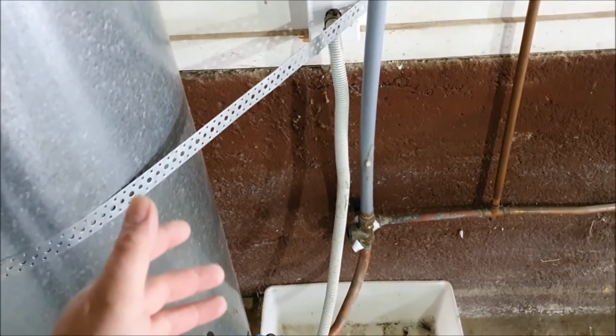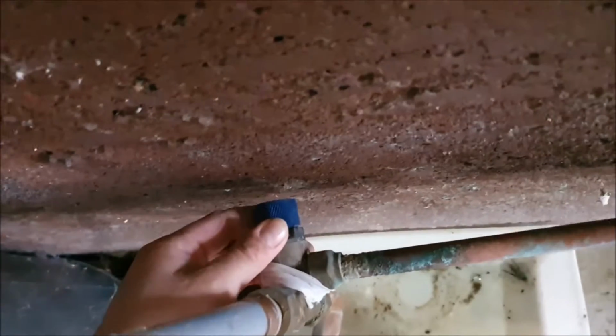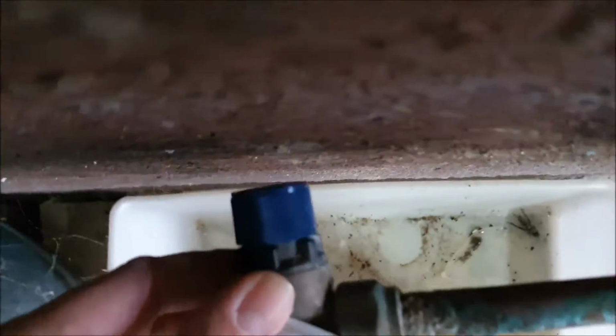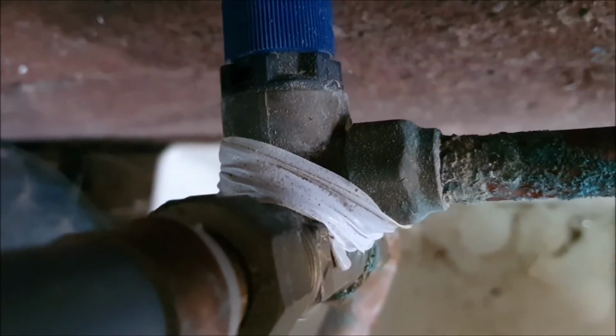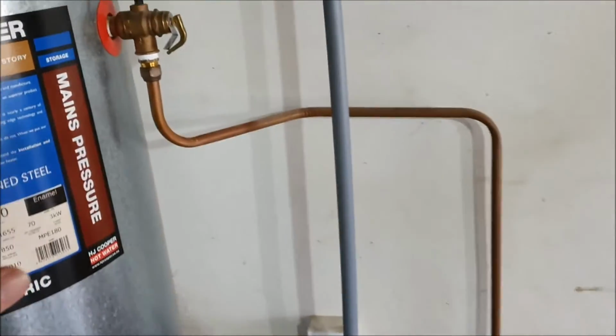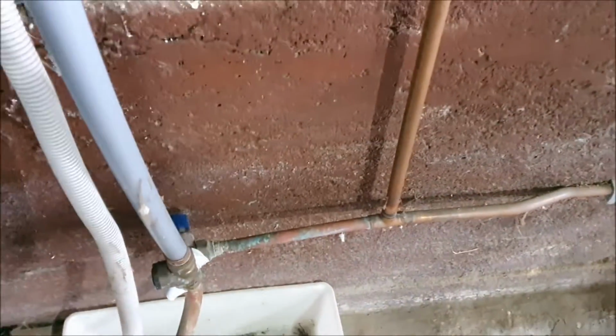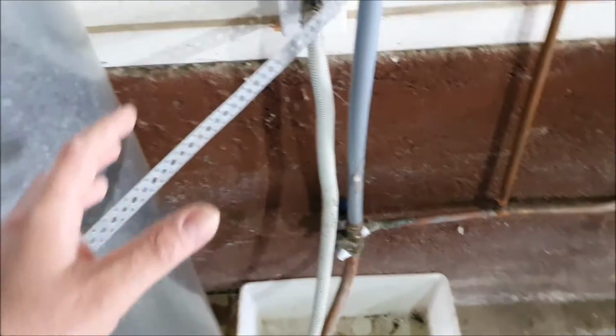Fourth major problem with this, whoever plumbed it up like this, it's supposed to be accessible and possibly readable. And if you listen carefully, you can hear the pss, pss, leaking through. So yeah, not happy with the setup. This pipe should be just going straight, then out, connecting. It could have been done better, basically.